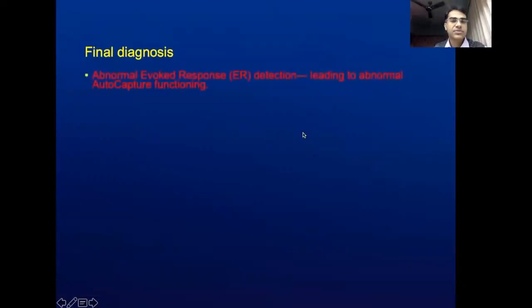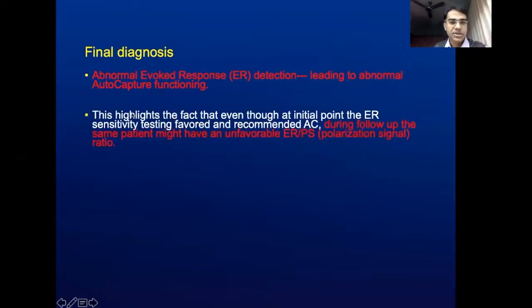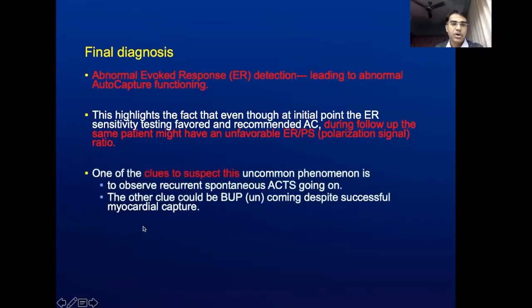So the final diagnosis for this patient was abnormal evoked response detection, leading to abnormal auto capture functioning, which kept on repeating the auto capture threshold testing. This highlights the fact that even though, at the time the patient underwent pacemaker implant, evoked response sensitivity testing favored and recommended auto capture, during follow-up the patient might have an unfavorable evoked response to polarization signal ratio. One of the clues to suspect this uncommon phenomenon is recurrent spontaneous auto capture threshold testing. The other clue could be an unnecessary or inappropriate backup pulse coming despite a successful myocardial capture. Our index case had both these features.